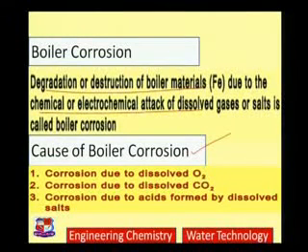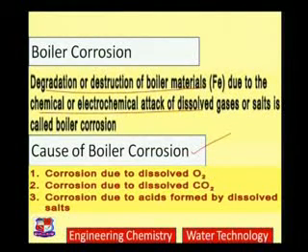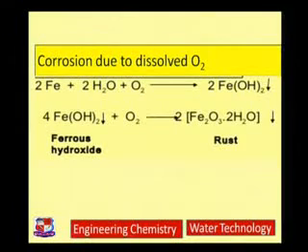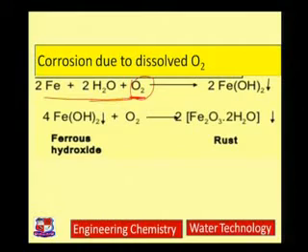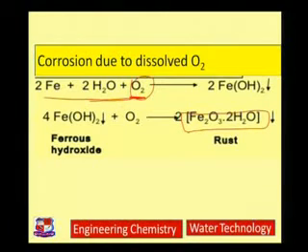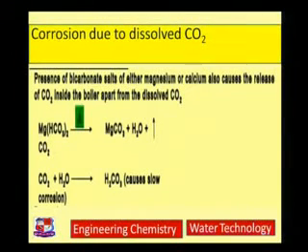A certain amount of oxygen is dissolved in water. When hard water containing dissolved oxygen enters the boiler, it may react with iron and cause rust formation or boiler corrosion. To avoid boiler corrosion due to oxygen, the water should be de-aerated. Regarding corrosion due to dissolved carbon dioxide: CO₂ is not generally present in significant amounts in water, but in hard water we have dissolved bicarbonate salts. Upon heating in the boiler, these bicarbonates get converted to carbonates and carbon dioxide is released.